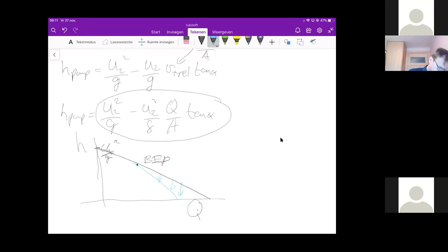And on this side, because then you are below the optimum situation, you get all kinds of friction loss and the flow doesn't follow the blades anymore. It goes something like this. And normally there's a minimum flow, Q min, and below that flow you get only eddies and all kinds of stuff within a pump. So this is important. The typical shape of the pump curve is really this one, the blue one here. This is the real shape, and the black one is the theoretical shape.